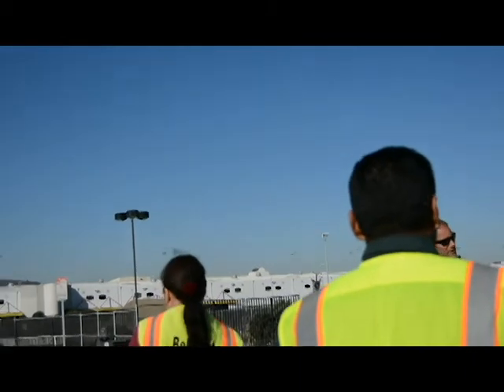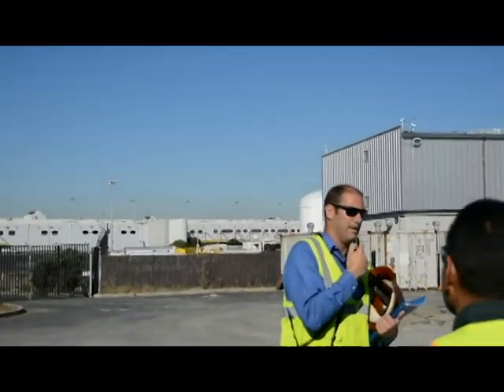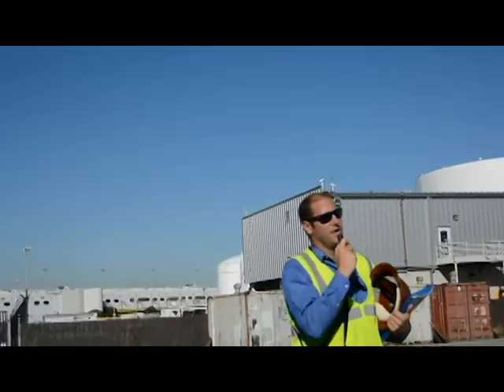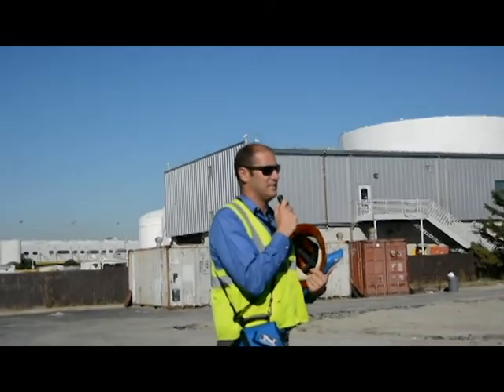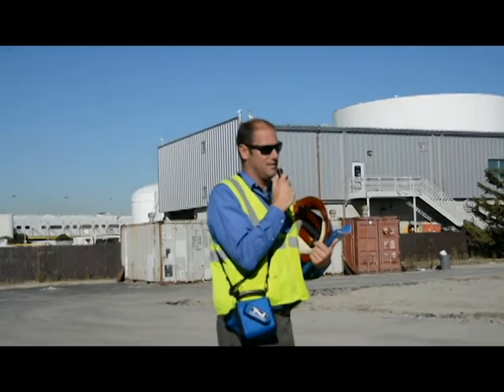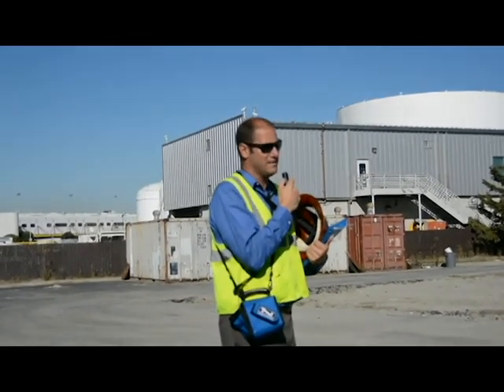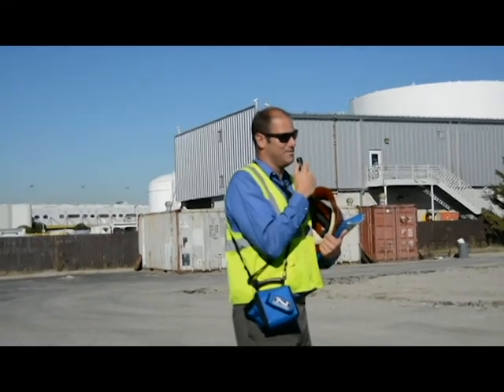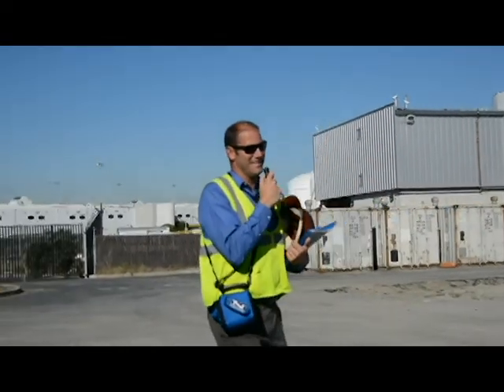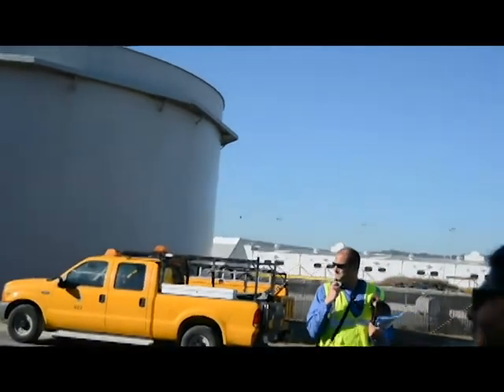So ambitious plans. We hope to offset between 25 and 50% of our potable water use on this campus by reusing this water. The major problem for us, though, is converting the SBRs to do nitrification, full nitrification. We need a fully nitrified water to use it and reclaim it. We do not have the space, the detention time to achieve that according to every consultant we've talked to, but we're going to do it in-house and we're going to do it ourselves, and we'll make it happen somehow. I'm pretty confident. You can start to look under our tank again.